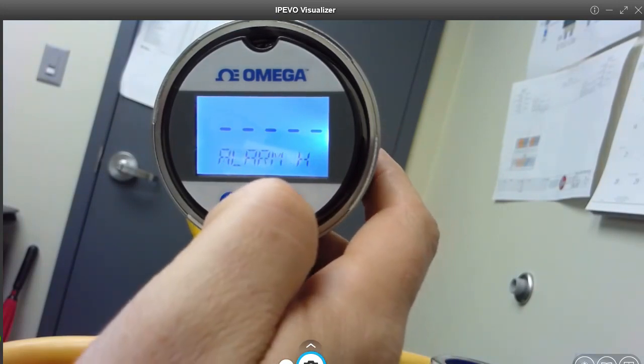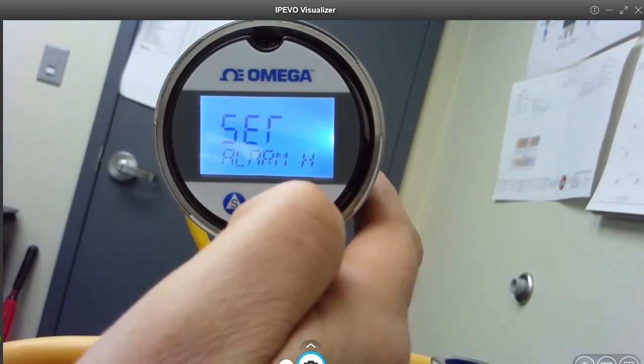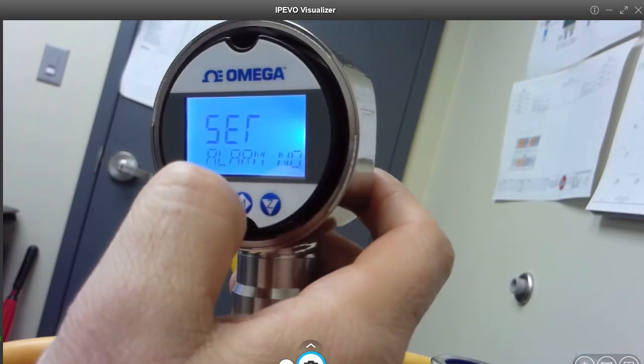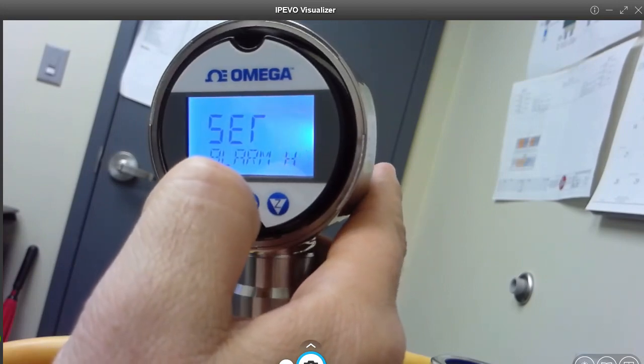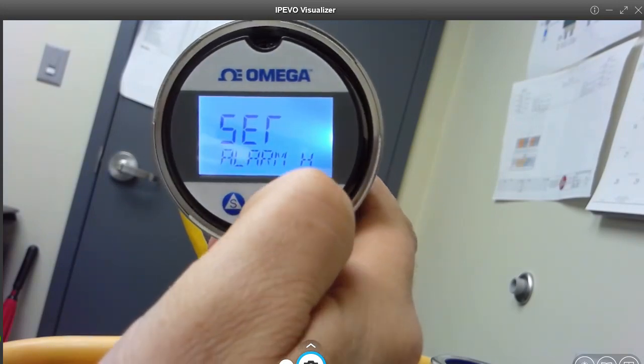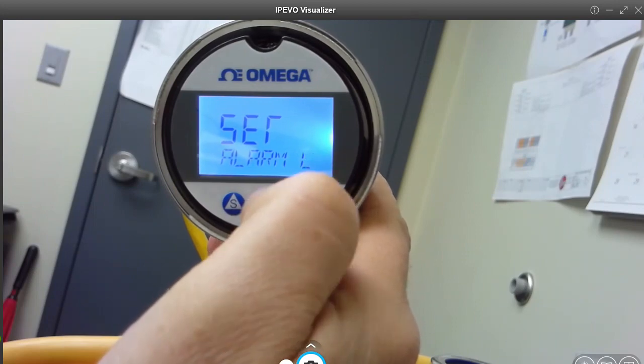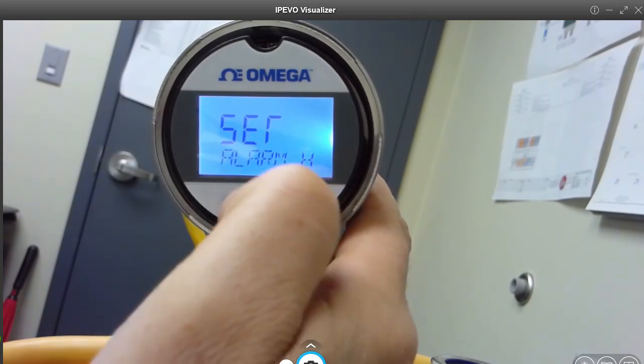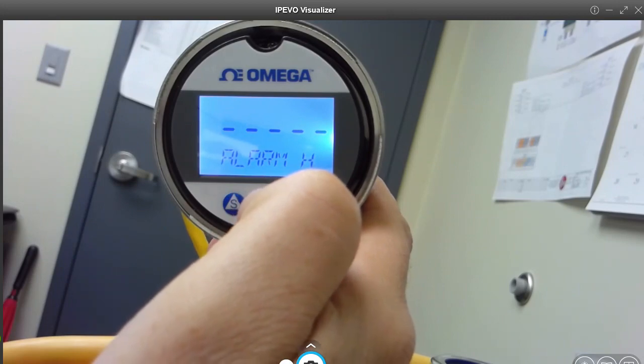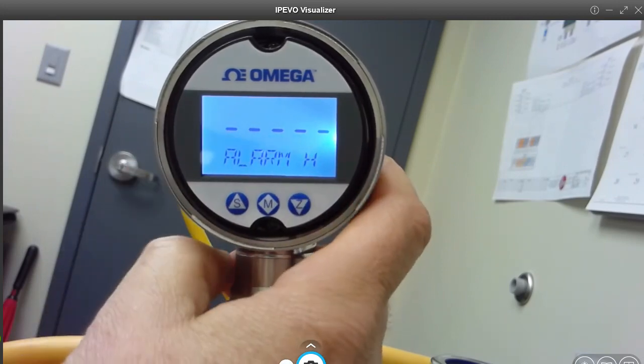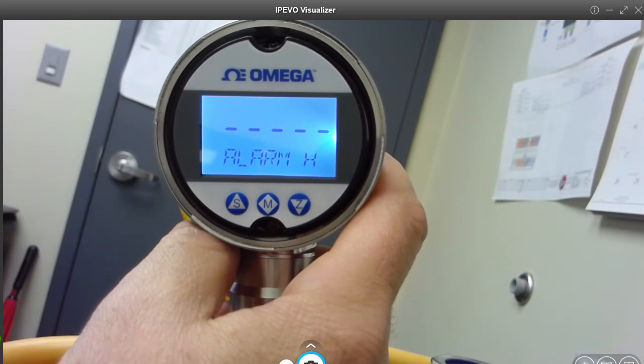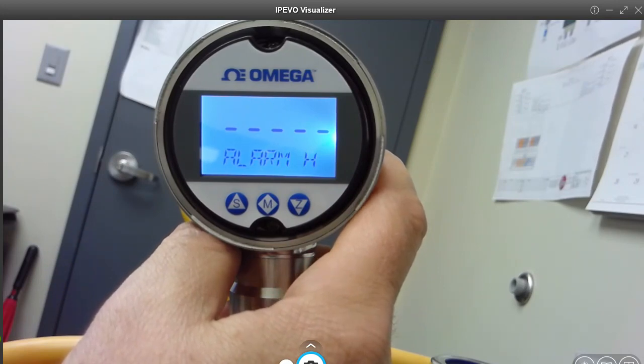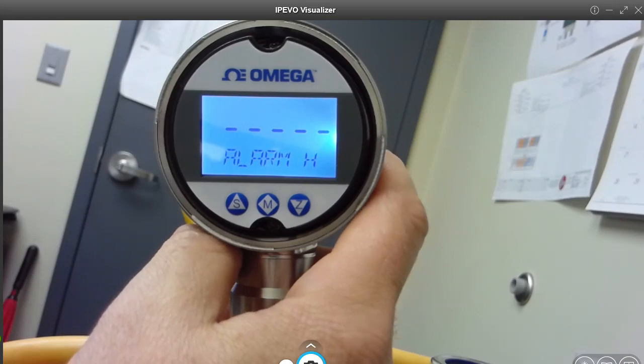Next, we want to make sure that our alarm is high. So if we want to see, alarm no is the default, we want to make sure alarm is set to high, alarm H, and hit the menu button. What this does is if this sensor faults and it can't see any pressure, like not even atmospheric pressure, then it will send a 20.8 milliamp alarm, a signal that will trigger an alarm on the panel view, on our analog alarms.